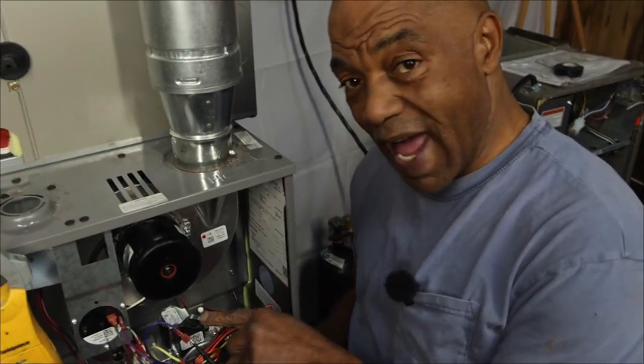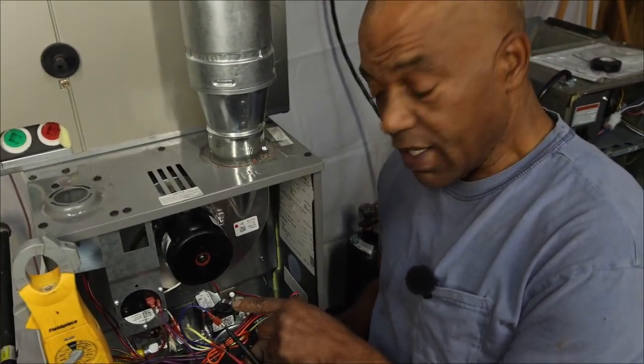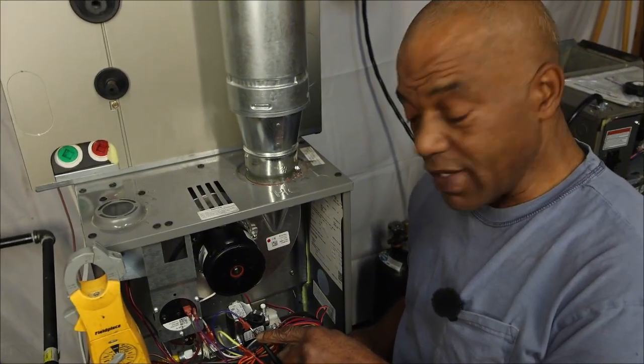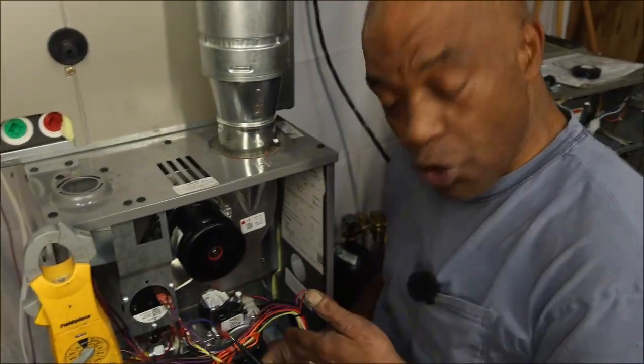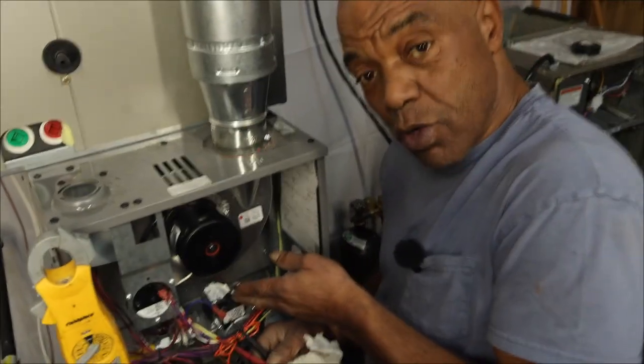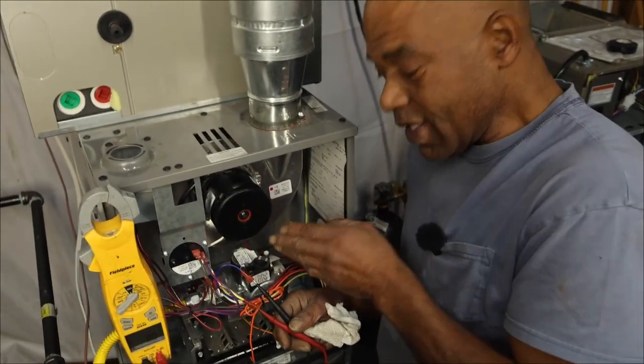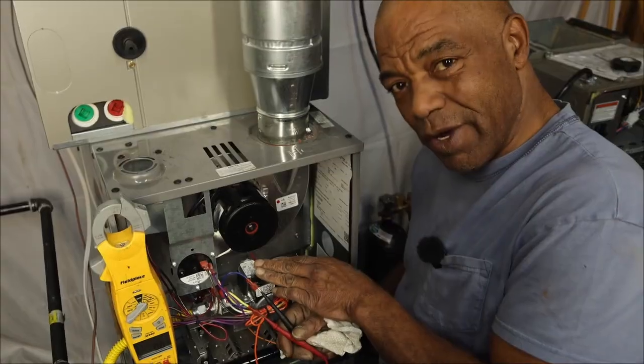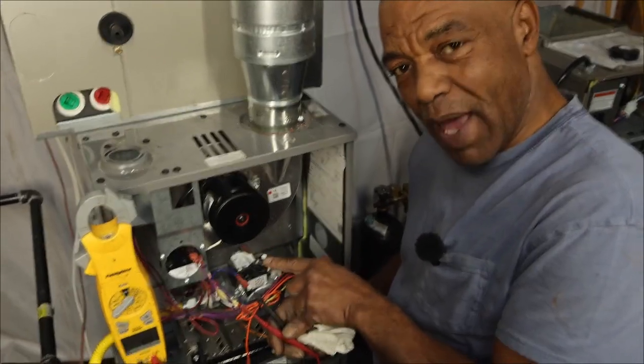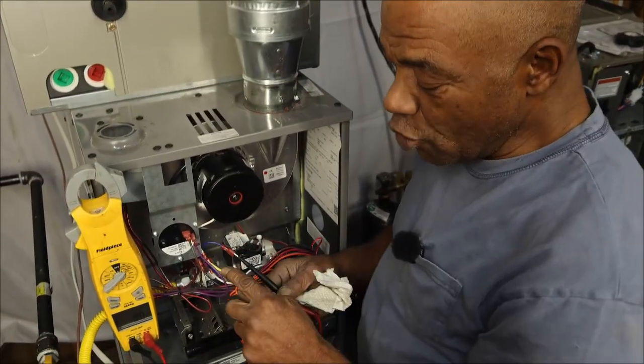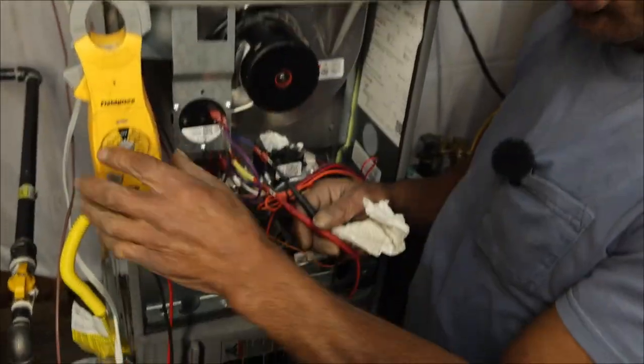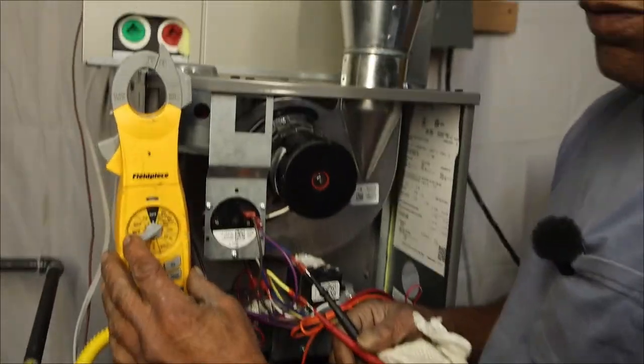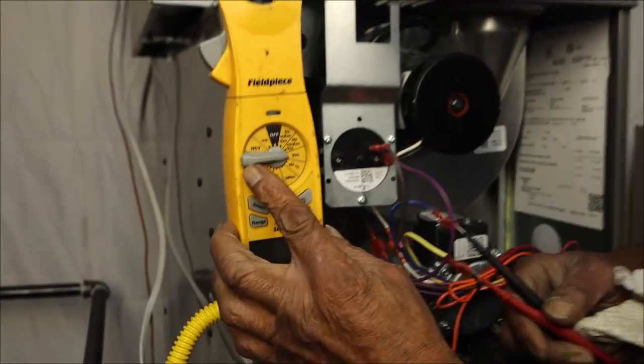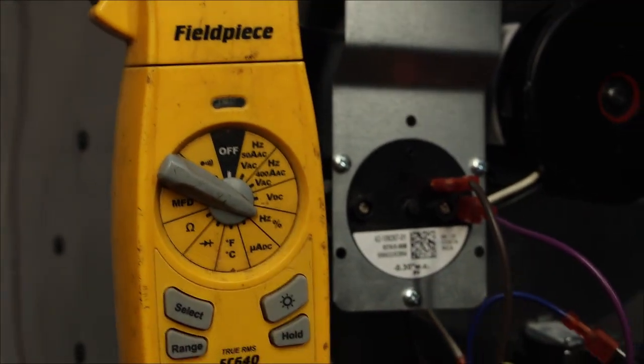So if my gas valve was not energizing, I just verified that the circuit board sent power to the gas valve. So now if it didn't fire, it must be bad. Those are different things you can use your multimeter for. As we go around, I'm going to show you in different videos.